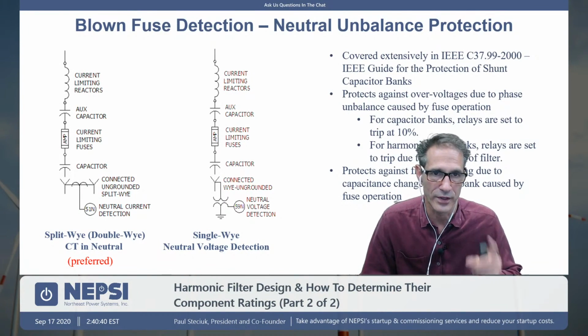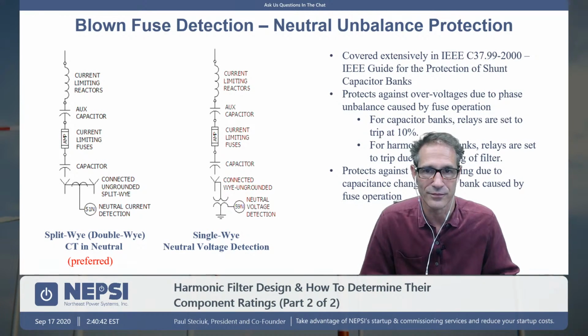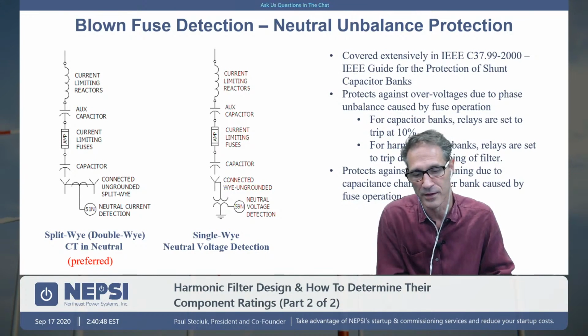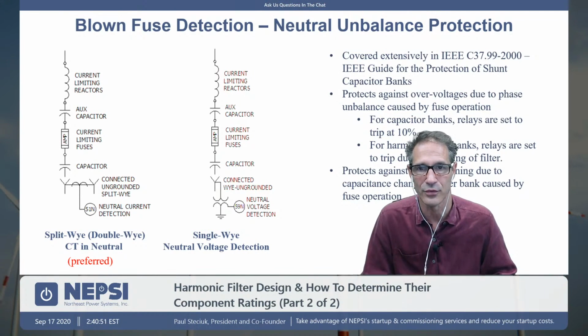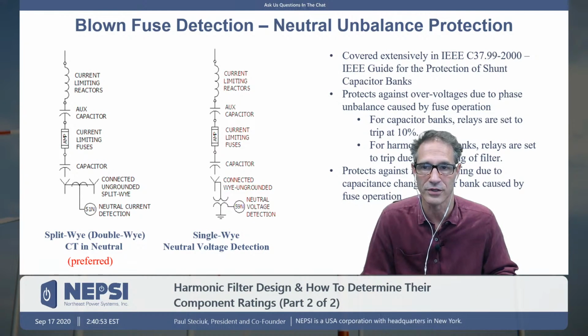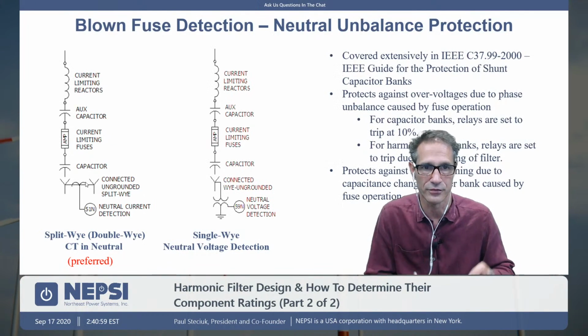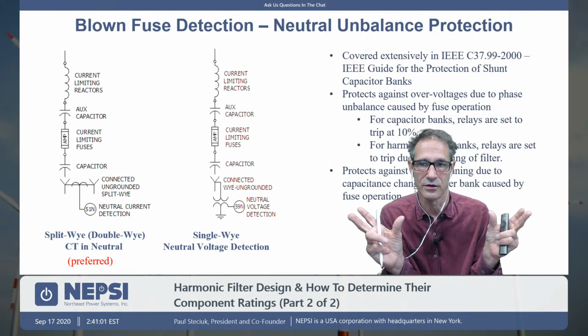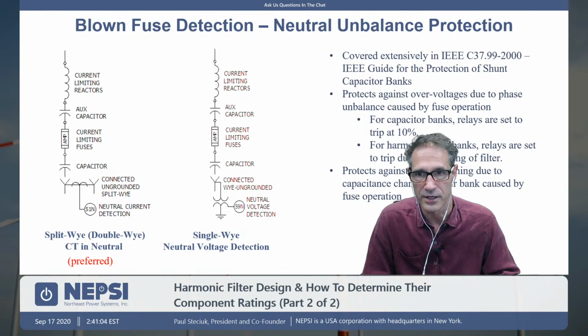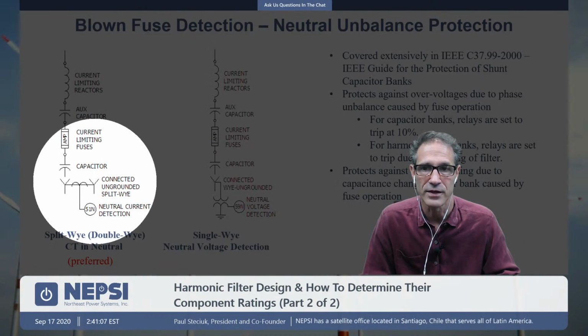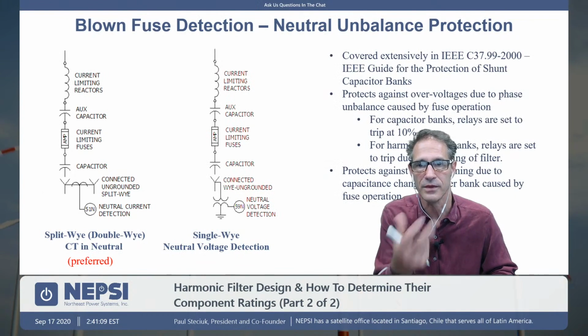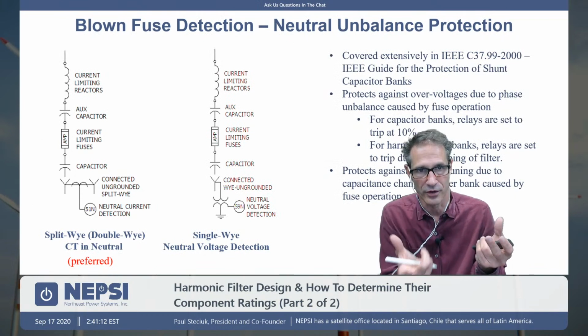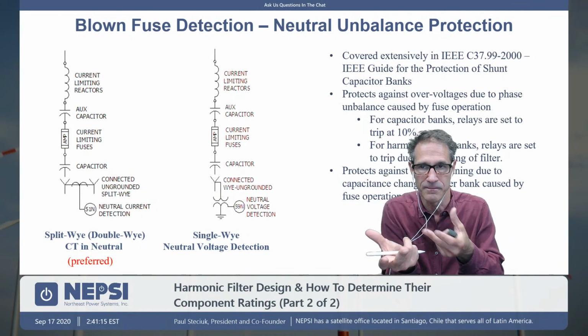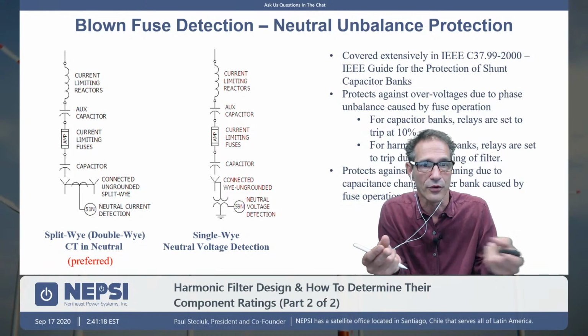I know for a fact that we have a tech talk, one of the early tech talks between 1 and 10, where we talked about neutral voltage and neutral current detection. So I encourage you to go back to one of those tech talks if you want to learn about neutral voltage and neutral current detection. On the left here, what we do is we split the capacitor bank into two individual Y-connected ungrounded capacitor banks, and we run a connection between the neutrals of the capacitor banks, and we put a CT in the neutral, and we detect current flow. When there is an unbalance between the two Ys, between the one capacitor bank and the other, I will get a current flow.